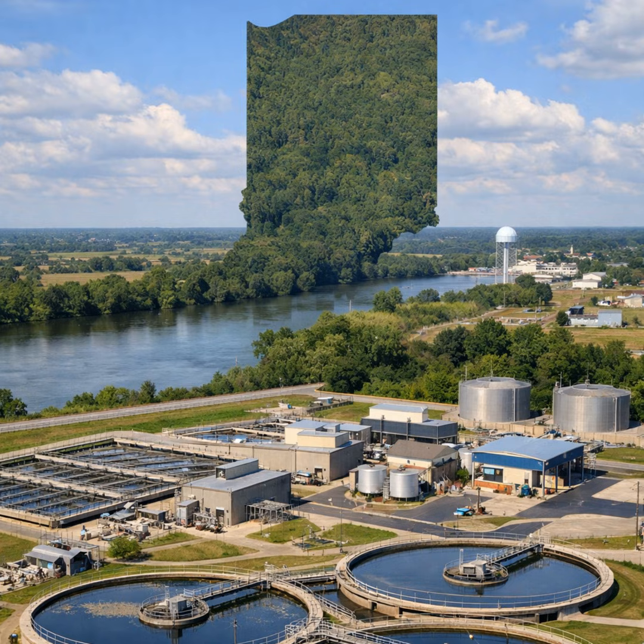Recalcination. Recalcination is a lime recovery process in which the calcium carbonate in sludge is converted to lime by heating it at 1,800 Fahrenheit, or 980 degrees Celsius. So, recalcination. Recarbonation is a process in which carbon dioxide is bubbled into the water being treated to lower the pH.